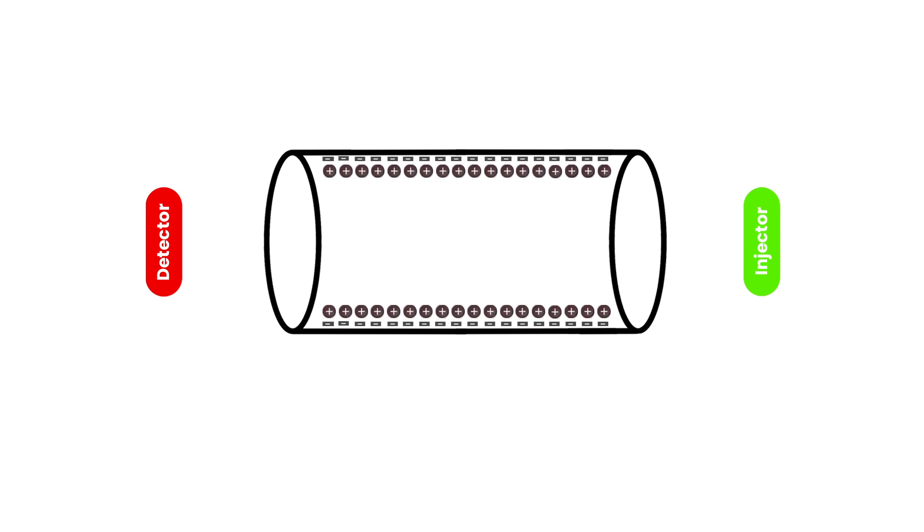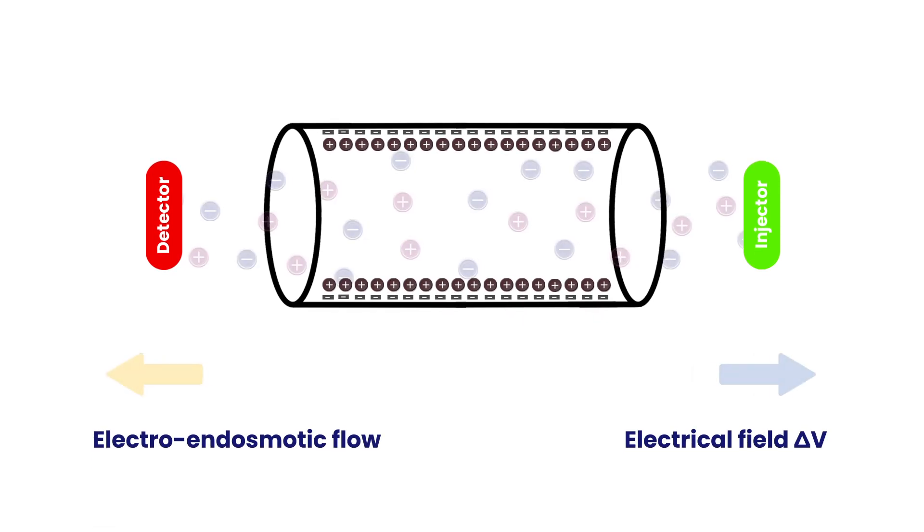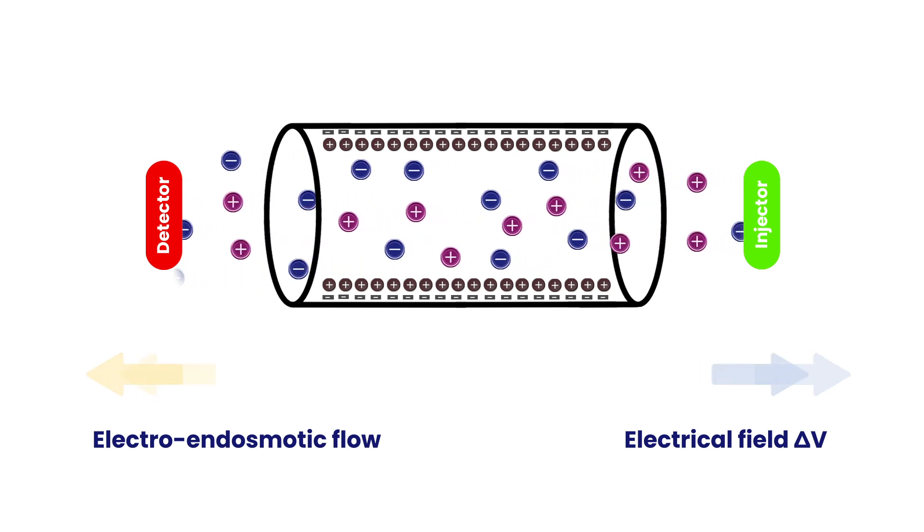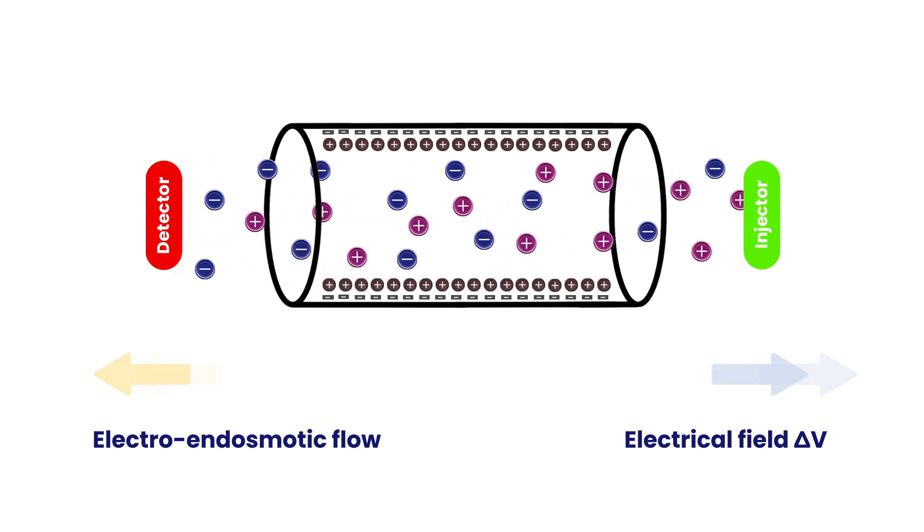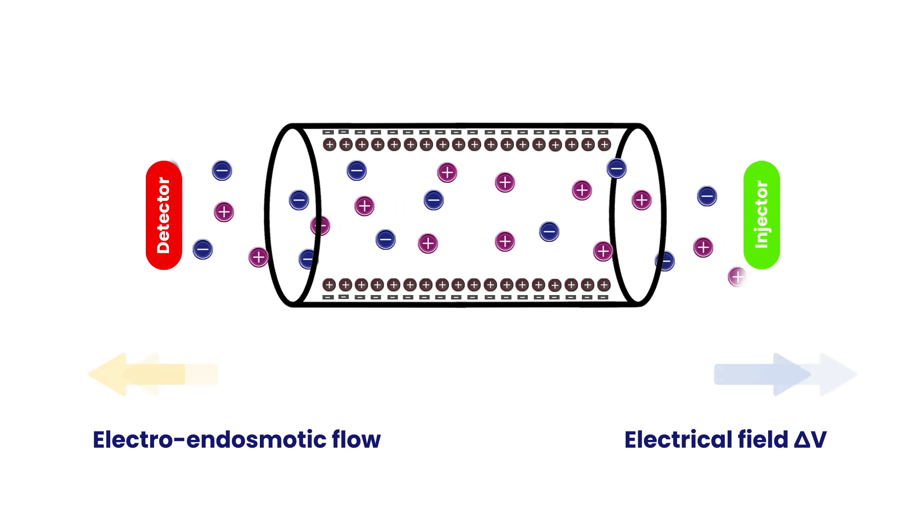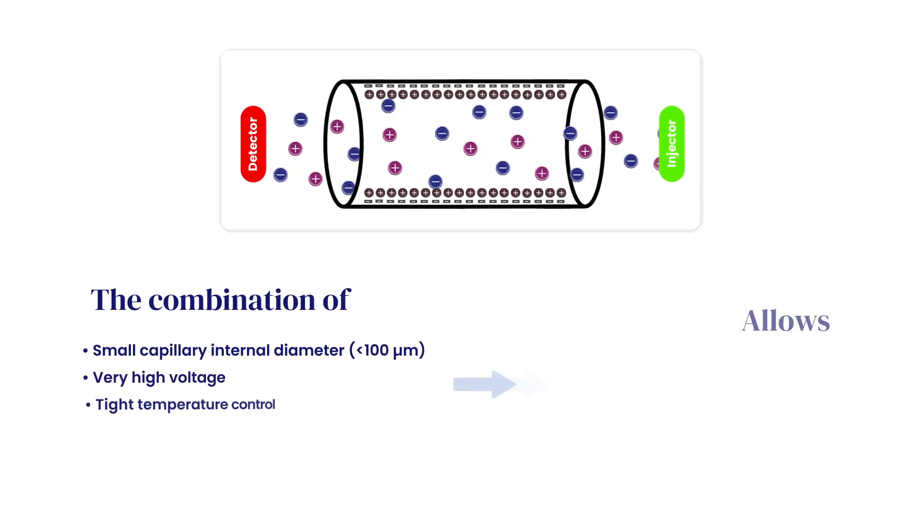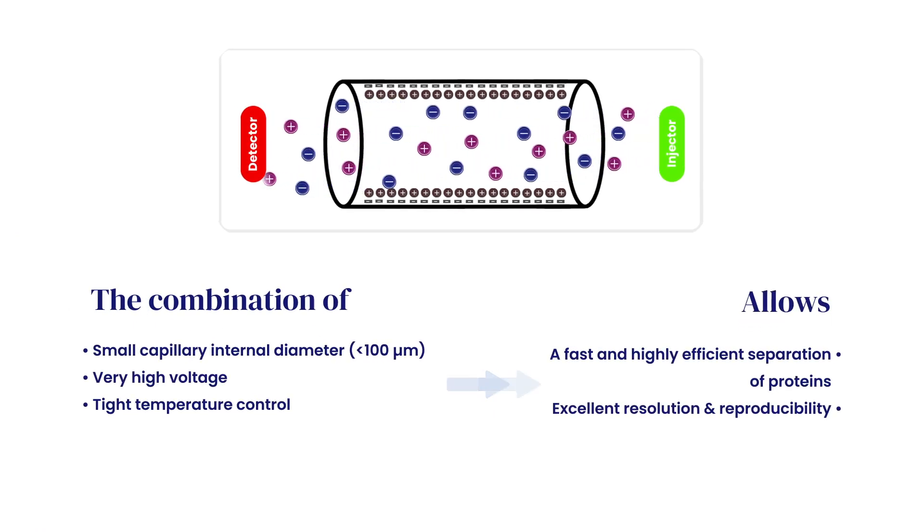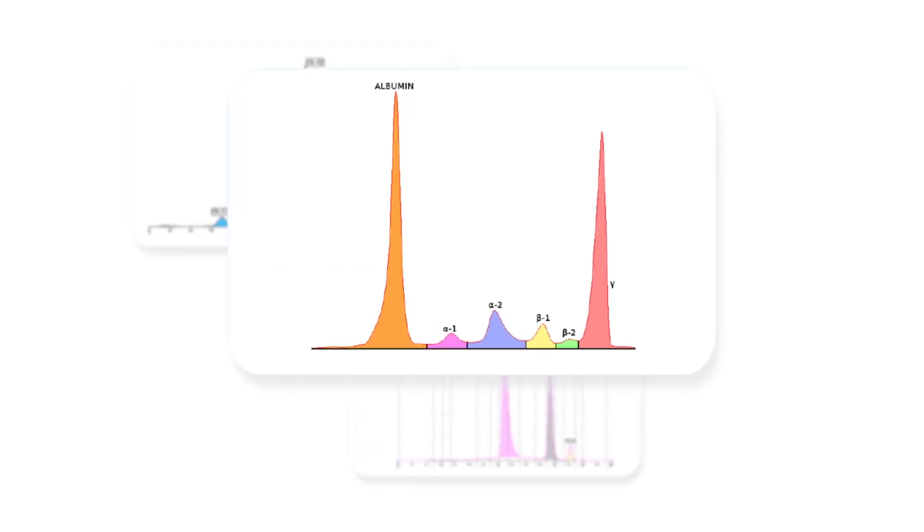Minicap uses the principle of capillary electrophoresis based on the electrokinetic separation in a capillary filled with electrolyte buffer. The separation occurs according to the electrolyte pH and electroosmotic flow. The combination of small capillary with internal diameter of less than 100 micrometers, very high voltage and tight temperature control allows a fast and highly efficient separation of proteins with an excellent resolution and reproducibility.